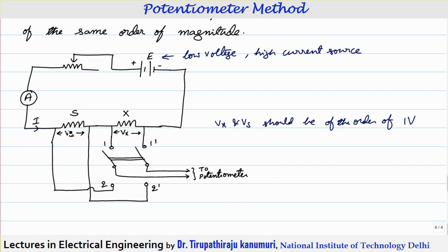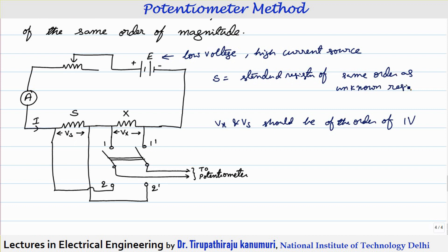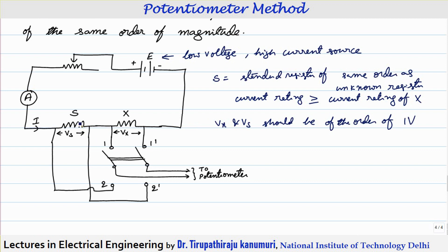Around 1 volt should appear across Vs and Vx, where S is the standard resistor of the same order as the unknown resistor — this is the first condition. The second condition is that the current rating of the standard resistor should be greater than or equal to the current rating of X, so that it will not get damaged.